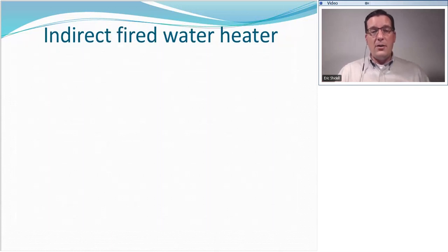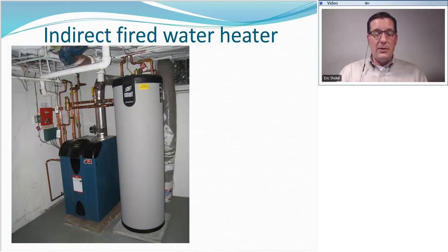Another kind of water heat exchanger is called an indirect fired water heater. It looks very similar to a standard electric water heater tank. And if you've never seen one before, it can be confusing because you will see domestic water pipes going into and out of it, and you will see boiler pipes going into and out of it. And that can make it seem as though the same water is in both pipes, but it's not.